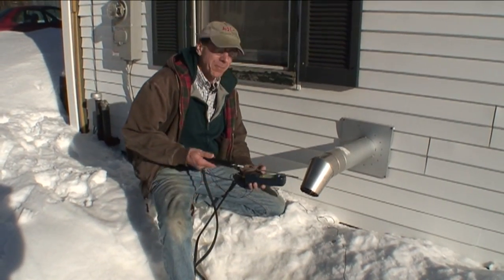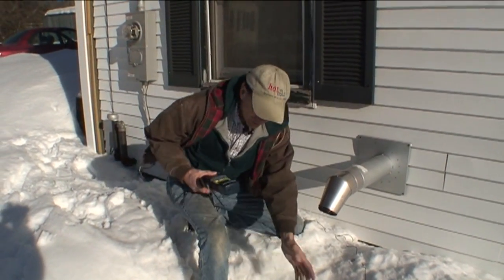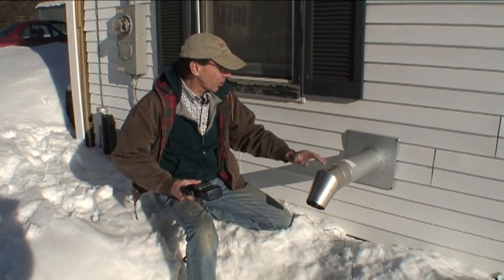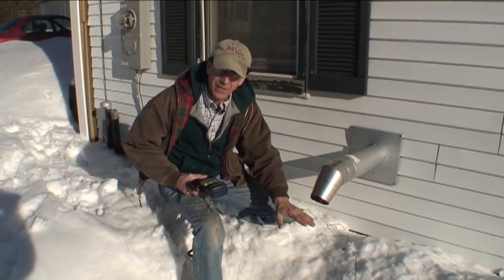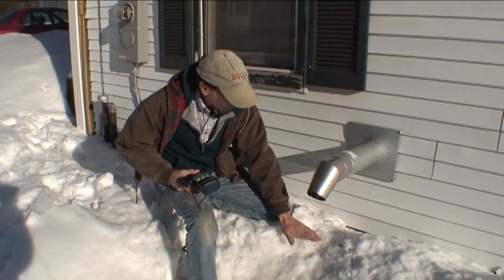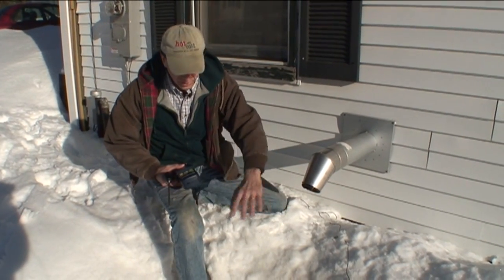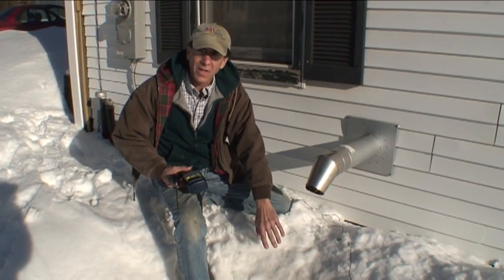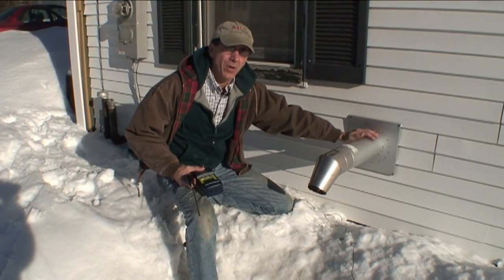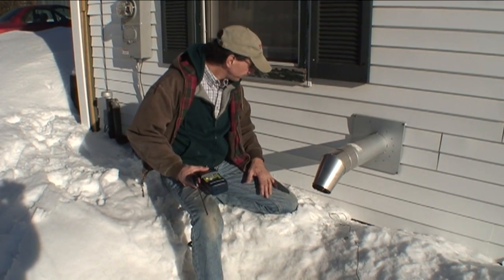We've got very good combustion efficiency. For people who know something about combustion, 13.8% CO2 is about where we want to be for most combustion appliances, and 60 ppm carbon monoxide is pretty decent — a good indication we're not having too little or too much air mixing in. You can see that a lot of heat has kept the area clear. We have a lot of snow sliding off this metal roof. It's always a concern that we don't have any impingement on the flue pipe — we want at least 12 inches of clearance between the ground or snow and the flue pipe.